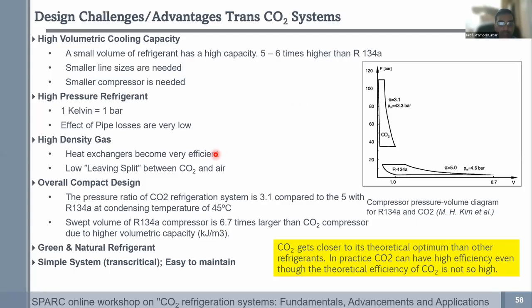The advantage of operating at significantly higher pressures is that, for example, 1 Kelvin is 1 bar, so the pipe losses are very low. You don't have to worry about pressure drops in the system. Heat exchangers, or the plates in a plate heat exchanger, can be very tightly spaced, and without a penalty on pressure drop, you can get significantly better performance. The flip side is that your system has to be built very well. If you have small issues, it can pretty much leak. The carbon dioxide will leak at an alarming rate, and within a couple of minutes the system will have vented out the carbon dioxide. That is one of the biggest disadvantages with carbon dioxide.